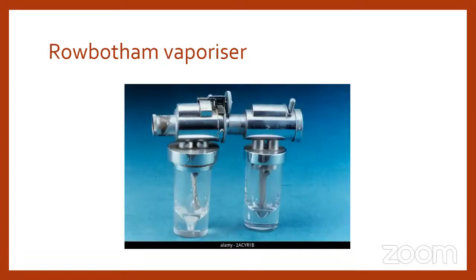And the next one is the Rowbotham vaporiser. It is basically the same as Goldman's vaporizer with a wick in the center. Basically, this wick will increase the surface area of the vaporizing chamber. So whenever the fresh gas enters the chamber, it has more contact area and more vapor will be incorporated into the fresh gas and delivered to the patient.